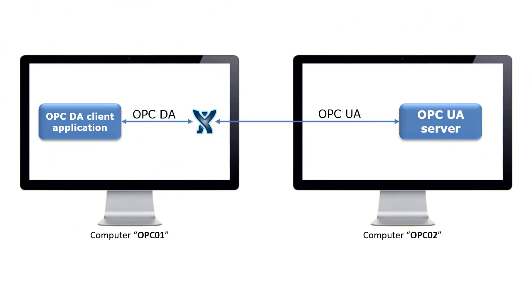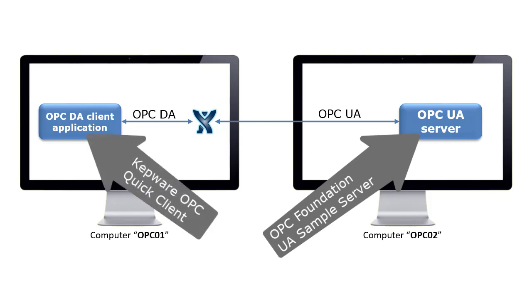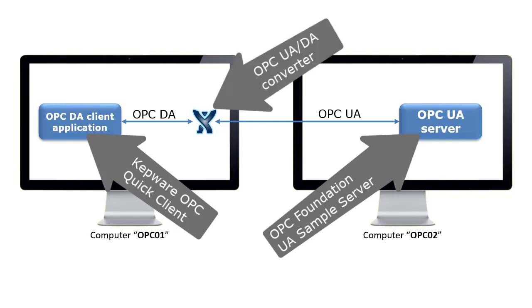In this example we are running OPC Foundation UA sample server on computer OPC 02. We have Kepware OPC Quick Client, which is an OPC Classic DA application, on computer OPC 01. Since OPC Quick Client is unable to connect directly to an OPC UA server, we need to put a converter in the middle.